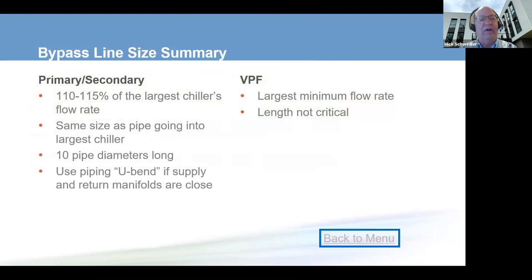So just to summarize, in a primary secondary system, 110 to 115% of the largest chiller's flow rate and 10 pipe diameters long. If it's shorter than that, put in a U-bend like we showed with a couple of elbows to impose a small pressure drop. In a variable primary flow, the length isn't critical because we have a control valve in that bypass line and it's sized for the largest minimum flow rate of all the chillers there. So that's bypass line sizing.